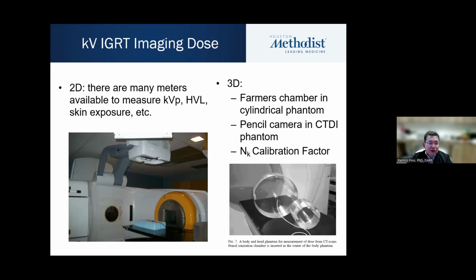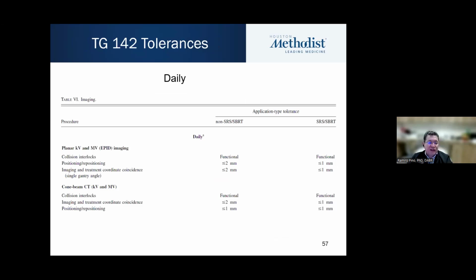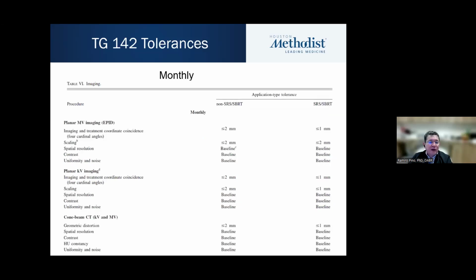For the kV IGRT imaging dose, there are many meters out there, and as I mentioned, it's a similar process using CTDI with the pencil chamber and the head and body phantoms. I'm mentioning here the TG-142 tolerances for daily, typically: collision interlocks, positioning and repositioning, and imaging and treatment coordinate coincidence, both for planar and cone beam CT. And the tolerances depend on what type of treatment you are trying to perform, whether it's 2D, 3D, or SRS or SBRT.